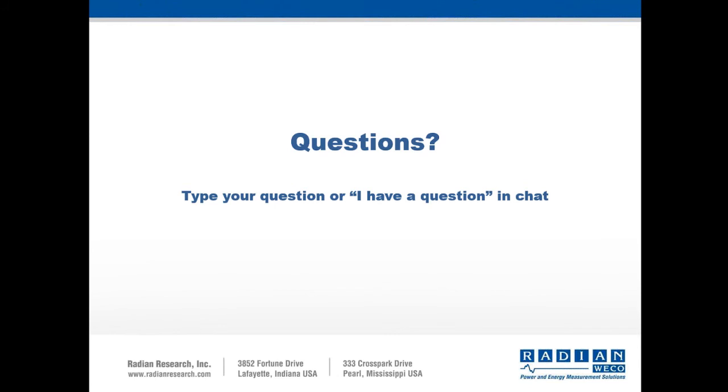First question I saw from Virgil: how often is the RMS value calculated with this recorder? The RW updates the RMS value on the physical UI roughly every second. The internal standard processes it a bit quicker than that, but in terms of UI and updating, it updates about every second or so in real time what you're seeing at the site. But the internal standard does it a bit faster than that, but we can only update the screen so quickly.